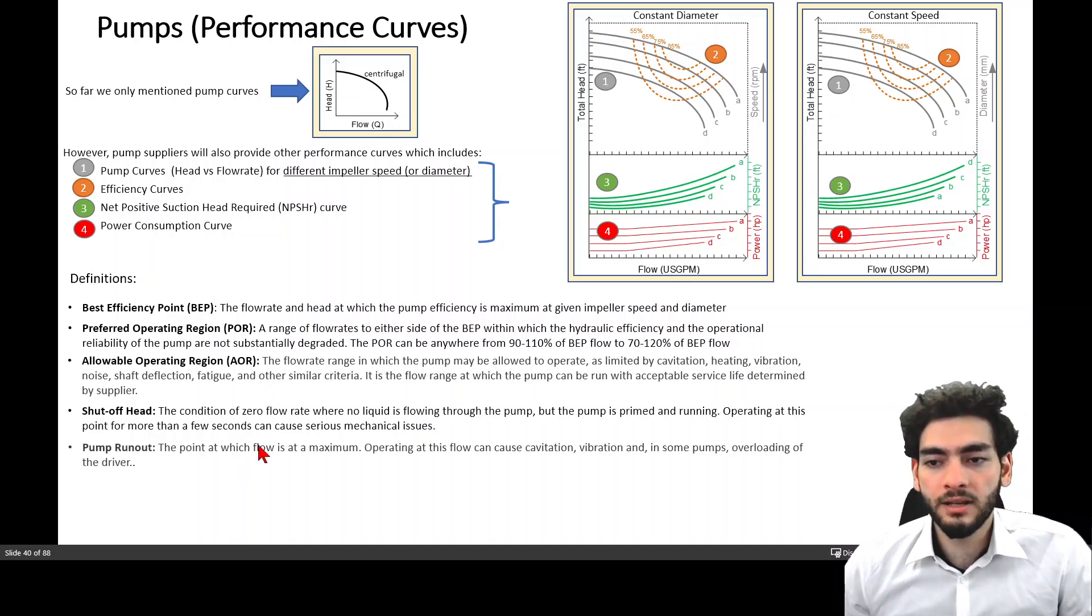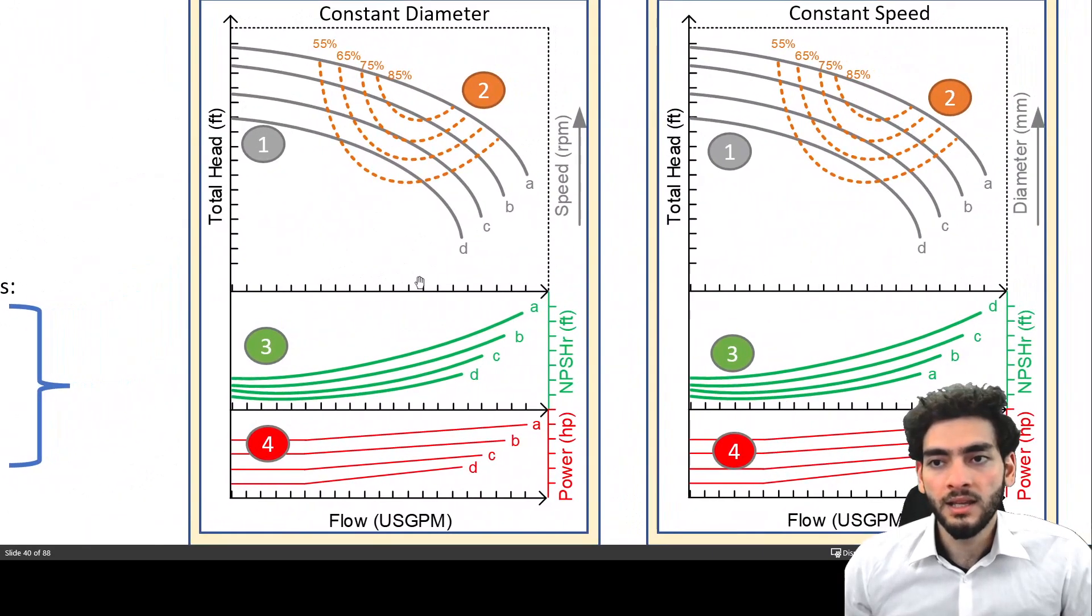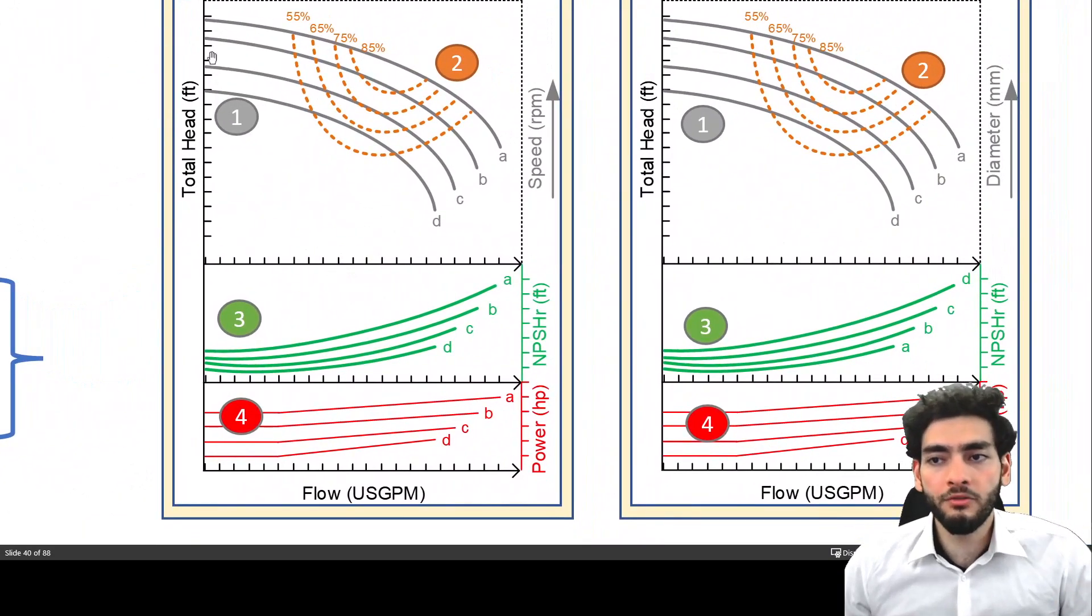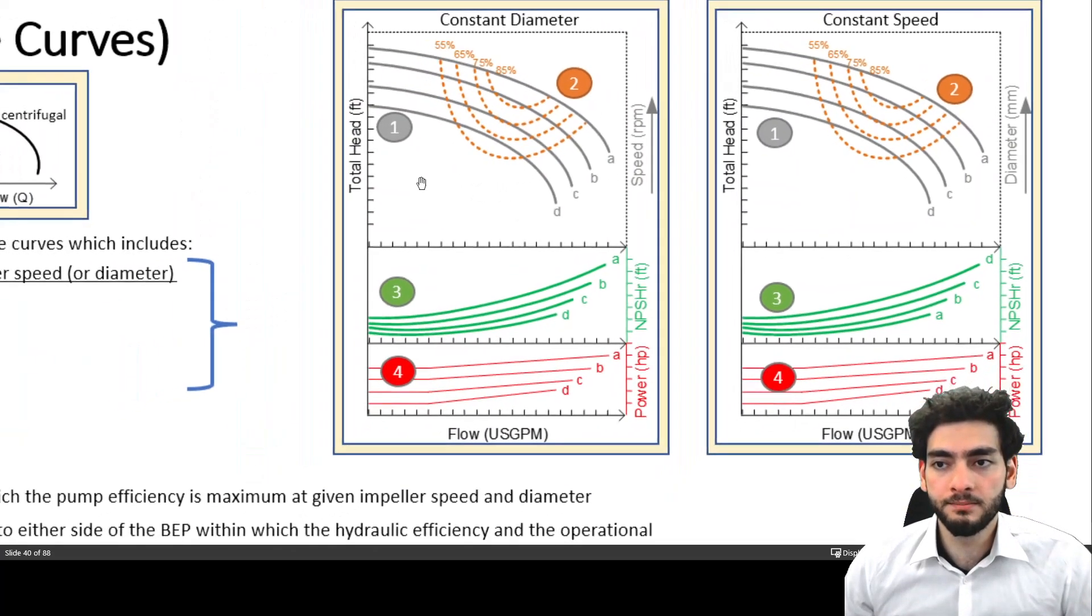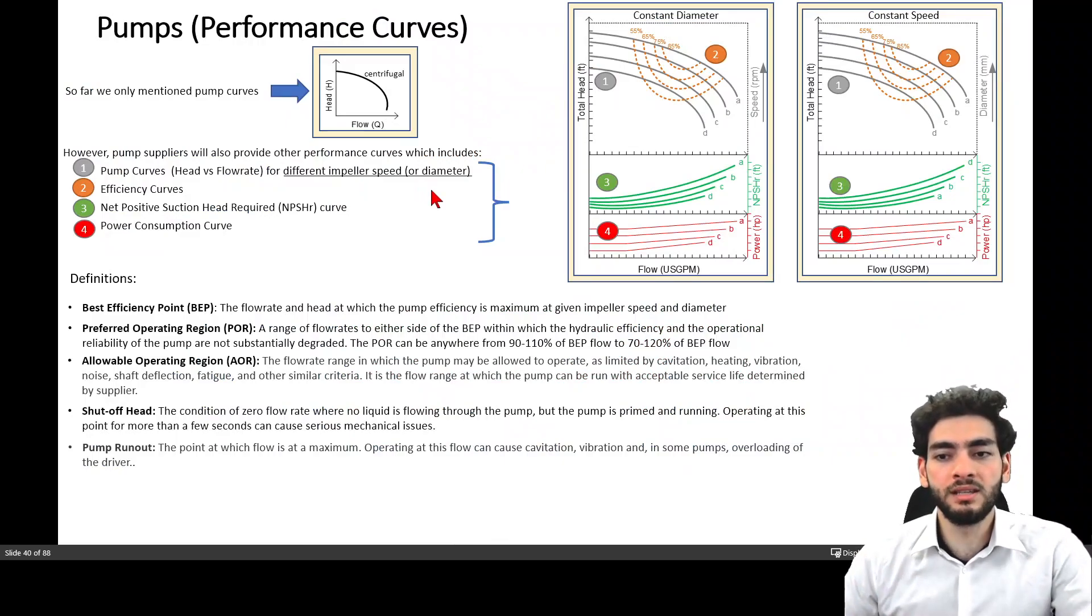Pump runout is the point at which the flow is at maximum. Operating at this flow can cause cavitation, vibration and in some pumps overloading of the driver. So as opposed to the shut off head, the pump runout is when you run very close to this dipping point of the pump and this is also beyond the allowable operating range of the pump and you should not be running at that point because you can cause serious damages to your pump.